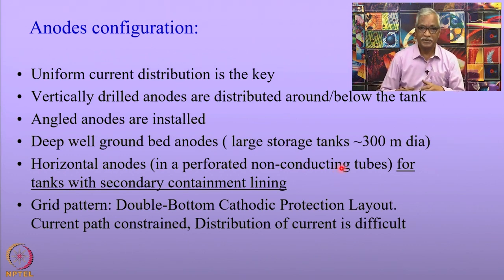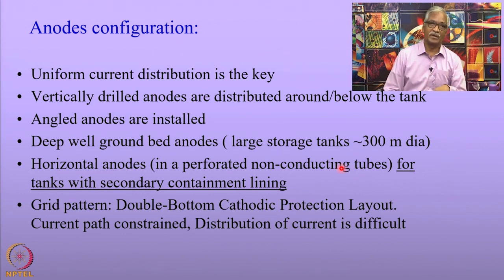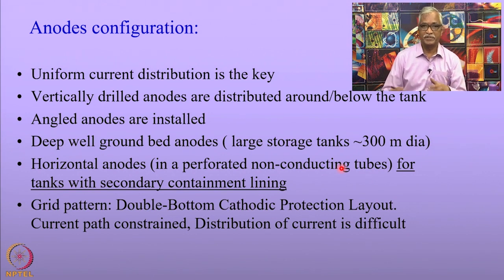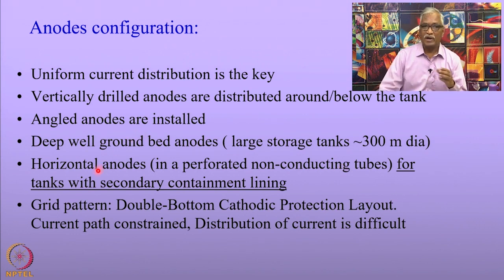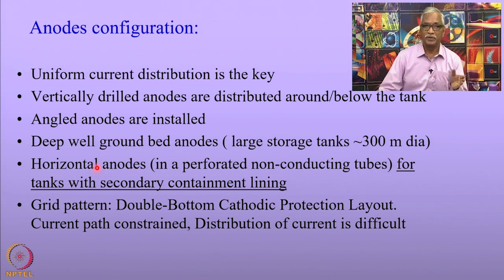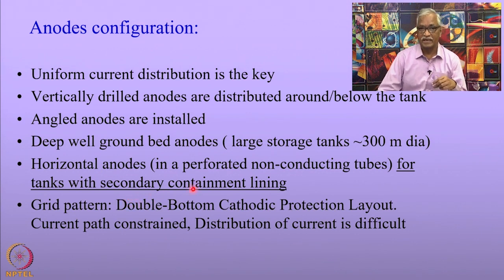With deep well ground bed anodes, the current distribution range is much larger and it is easy to maintain a remote anode. Horizontal anodes are also used where deep well ground bed anodes are not possible, and for tanks with secondary containment linings.